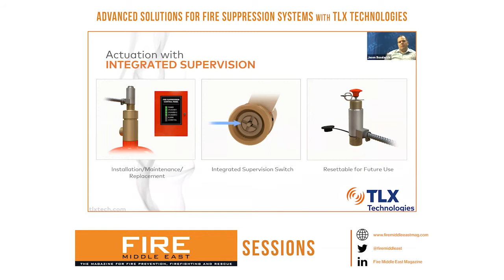The pin state monitoring device is really complementary to the integrated installation supervision. As Jason mentioned, say during maintenance the actuator is removed from the discharge valve, the installation signal lets us know this actuator did not get put back in place. The pin state monitoring allows us to know what state the pin is in, whether it's in the latch state, which means you could put it on the discharge valve, or in the fired state, where the pin is delatched or extended out of the body.